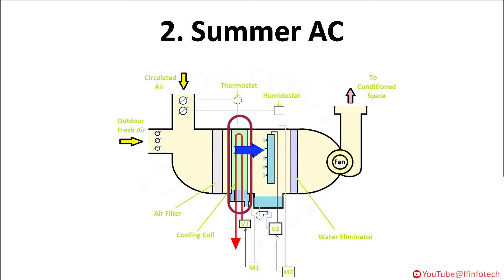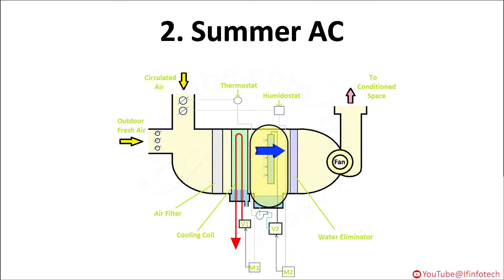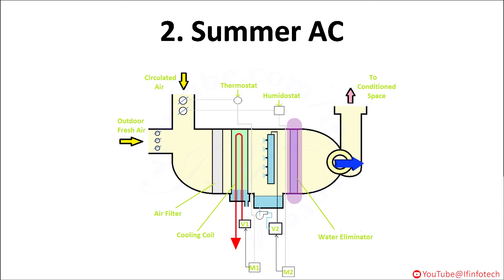The temperature of air is reduced with the help of the cooling coil. Coolant is circulated through the cooling coil and temperature of air is controlled with the help of coolant quantity. Removal of moisture is accomplished by condensation of water on the cold coil surface, where excess moisture is removed from air. Air is then passed through a spray type humidifier where air humidity is increased up to the required condition. The relative humidity of air is controlled by controlling the quantity of water spray. Air is then passed through a water eliminator where water droplets are removed before supplying air to the air conditioning space.